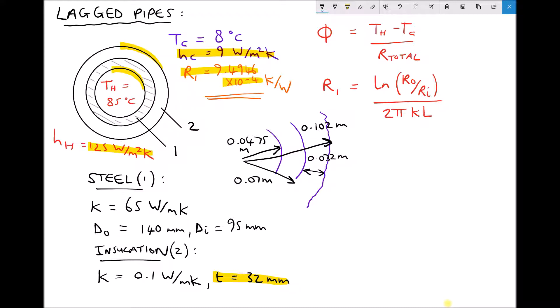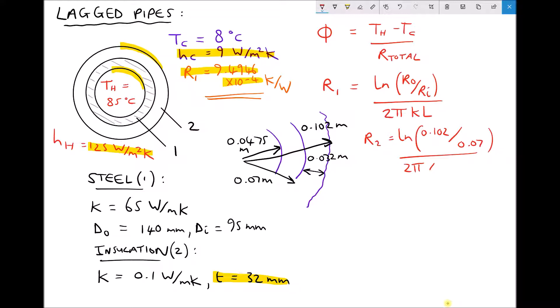We already have R1 for the steel, so we are just going to calculate R2. R2 is the natural log of the outside radius of the lagging, 0.102, divided by the inside radius of the lagging — which is the same as the outside radius of the pipe, 0.07 — divided by 2 pi times the thermal conductivity, 0.1, times the length. We are doing our calculations per metre of length. This gives us a value of R2 equal to 0.5992 Kelvin per watt.